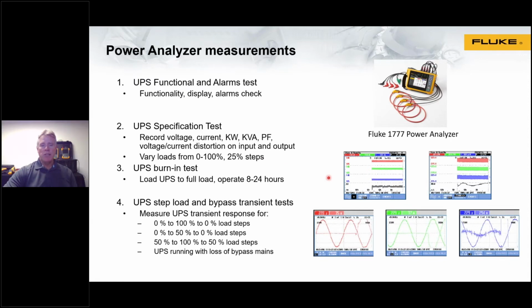This would be maybe an example of what you might see on a power analyzer over time. What you would need in the power analyzer essentially would be that capability to not just measure, but record that data over time, and to be able to save that and then generate upon request a test report. So the two images to the right are good examples of that burn-in test recording or a trend over time.